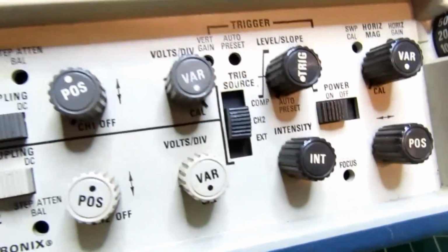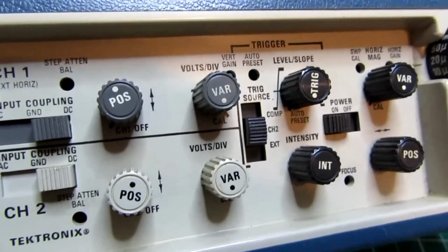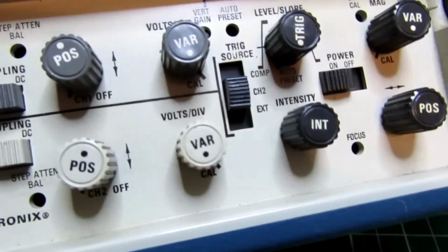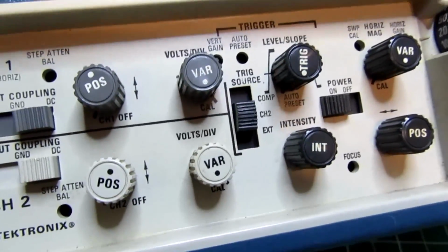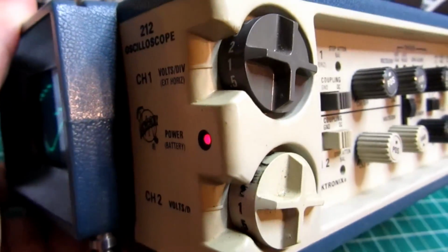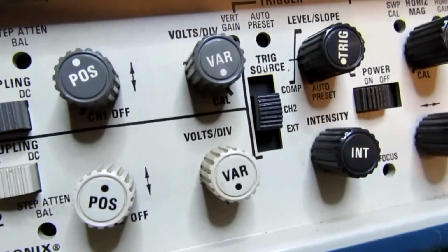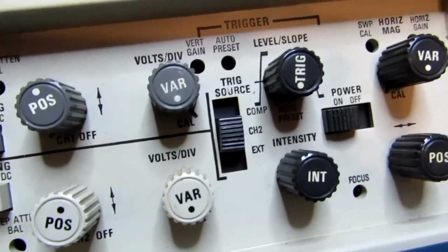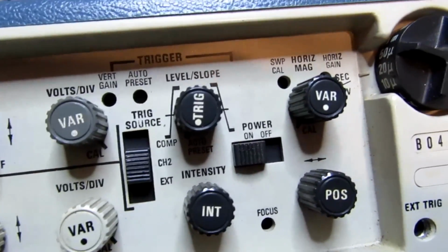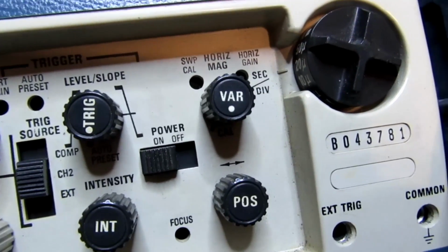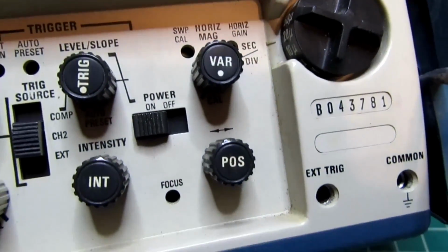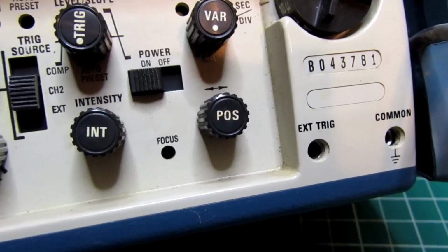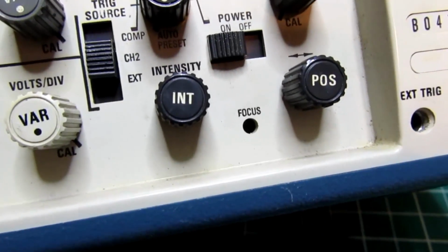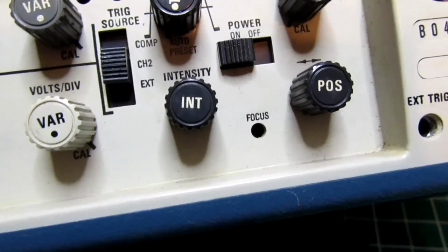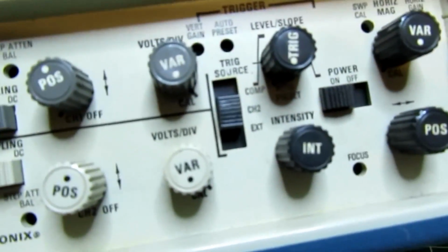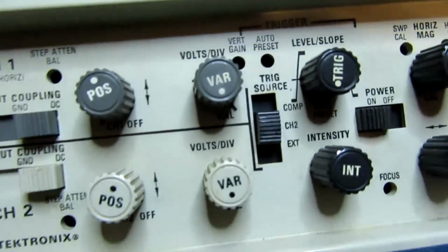And then you've got your variable volts per division control. If you've got it turned fully clockwise, then it's in the calibrated settings selected by the knobs up here, but otherwise you can adjust it freely with the small knobs. Then you've got your horizontal magnification control and your horizontal position control. There's also focus. It's not done with a knob here. You have to put a screwdriver in. Power switch. The trigger sources are a little bit unconventional.